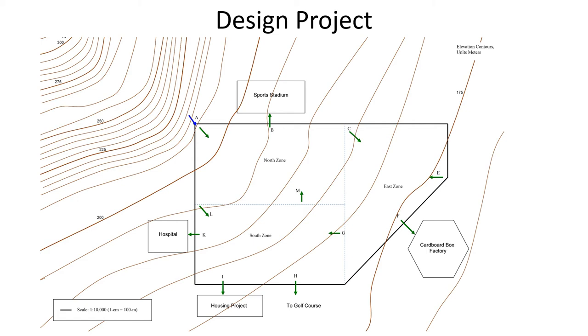After you estimate how much water they need, you're going to design how big the pipes should be. Sizing the pipe balances two things: you're balancing the cost of the pipe — trying to keep the cost low means making the pipe as small as possible — but you also want to deliver enough pressure to people using the water in this development. To develop adequate pressure at all points in the network, the pipe should be big. So you're bumping up against these two constraints: minimize pipe size but also ensure you're not going below a certain pressure limit.